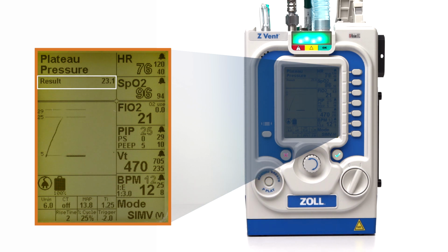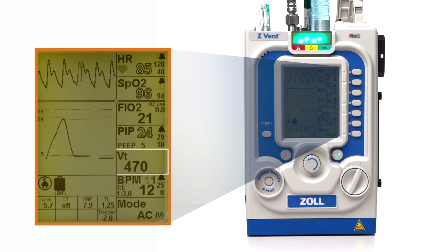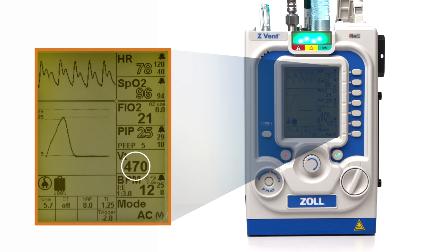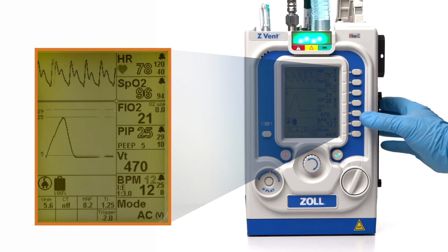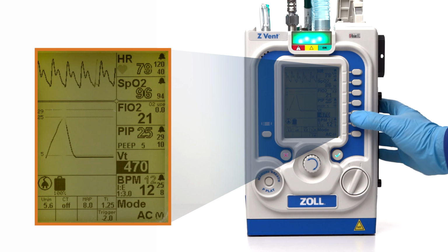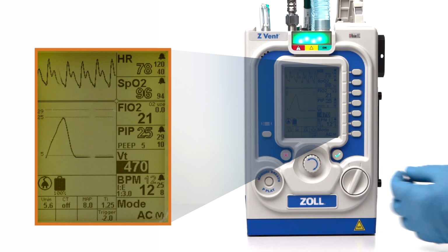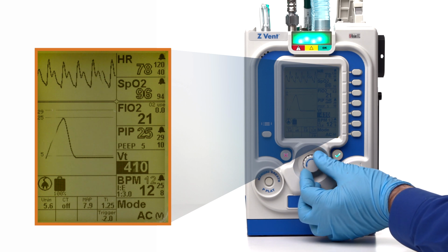The fifth window is tidal volume. When operating in volume-targeted breathing mode, the tidal volume is a solid numerical value and can be changed. The tidal volume can be adjusted from 50 to 2,000 milliliters. Press the parameter button once to change the desired tidal volume.